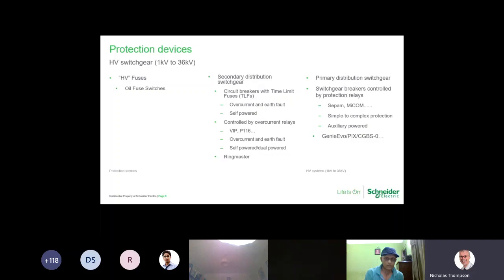When we move into the more technical switchgear, this is going to be your primary distribution switchgear, whether it's going to be 33 kV or 11 kV or 6.6 kV, where the technical requirements are much greater. You may need a much higher fault current protection, so above 21 kA fault level, for instance. You're coming across protection schemes which are ranging from relatively simple to something which is quite complex. And this is where we start to see the auxiliary powered relays and brands of Sepam, MiCOM, etc. are now going to be used as standard within that type of equipment.